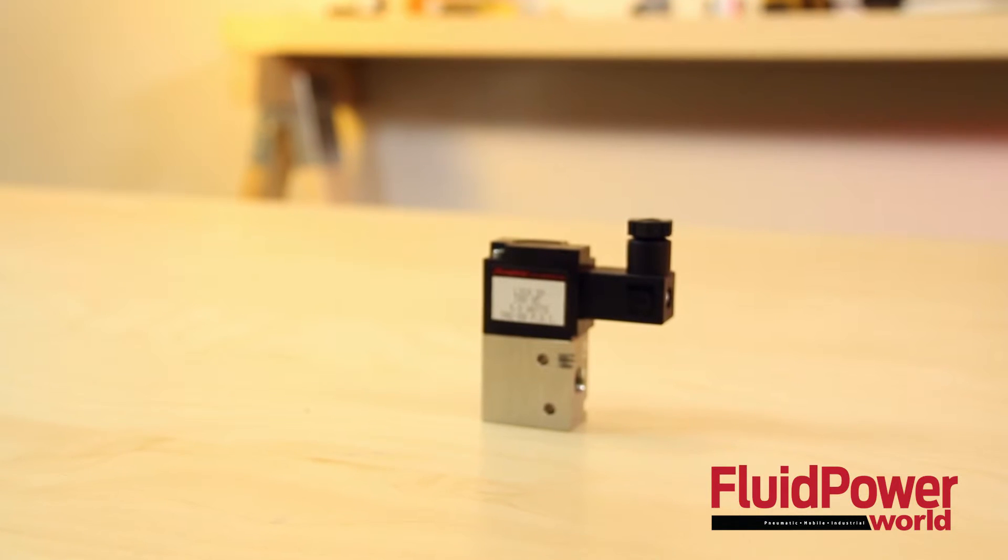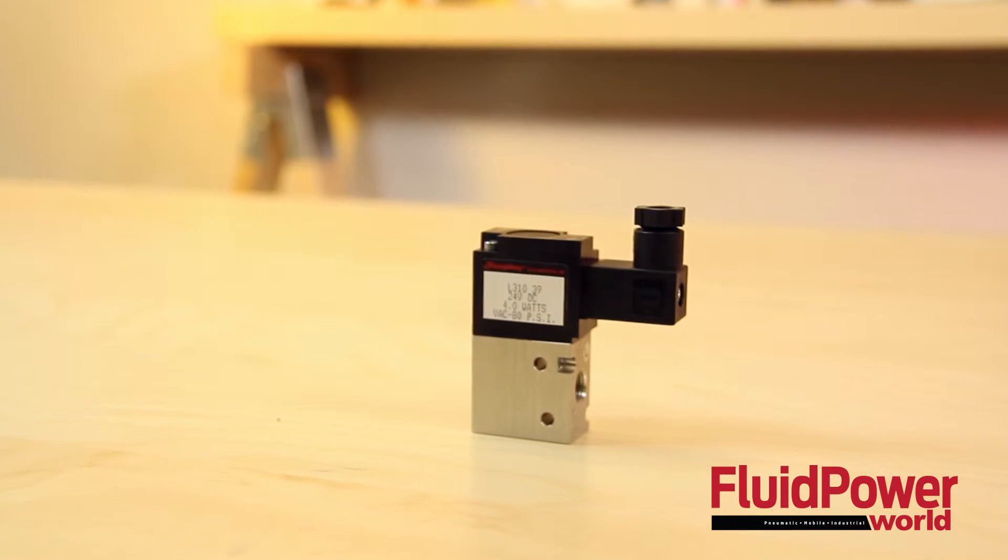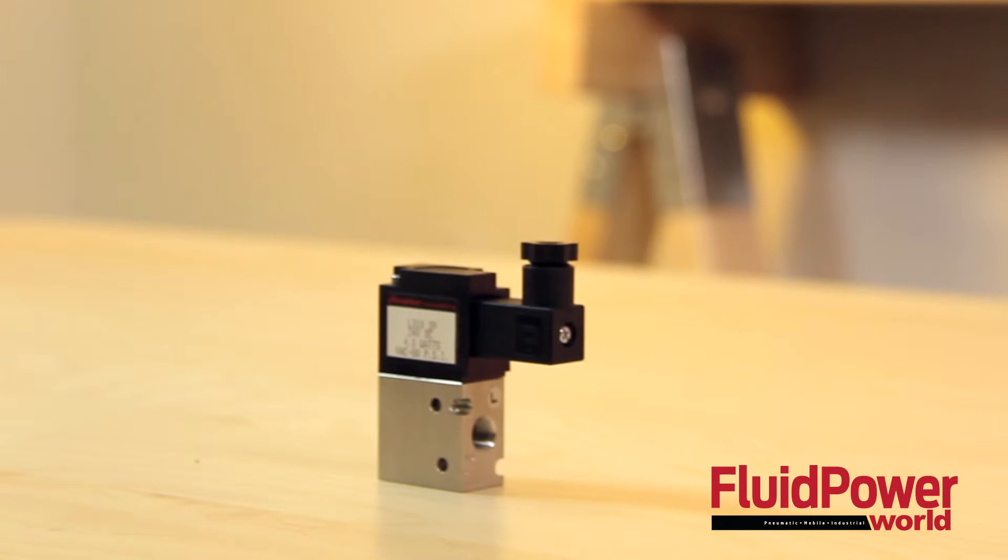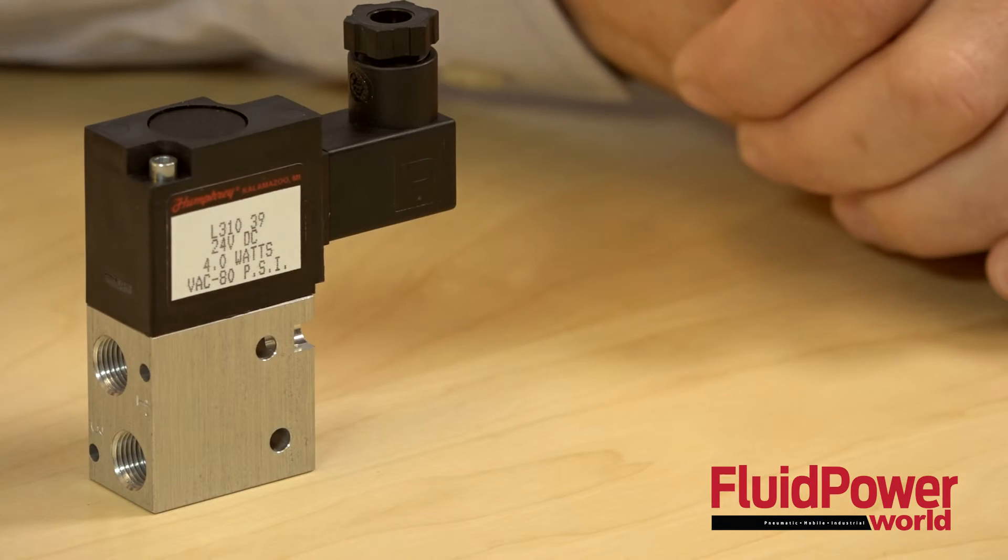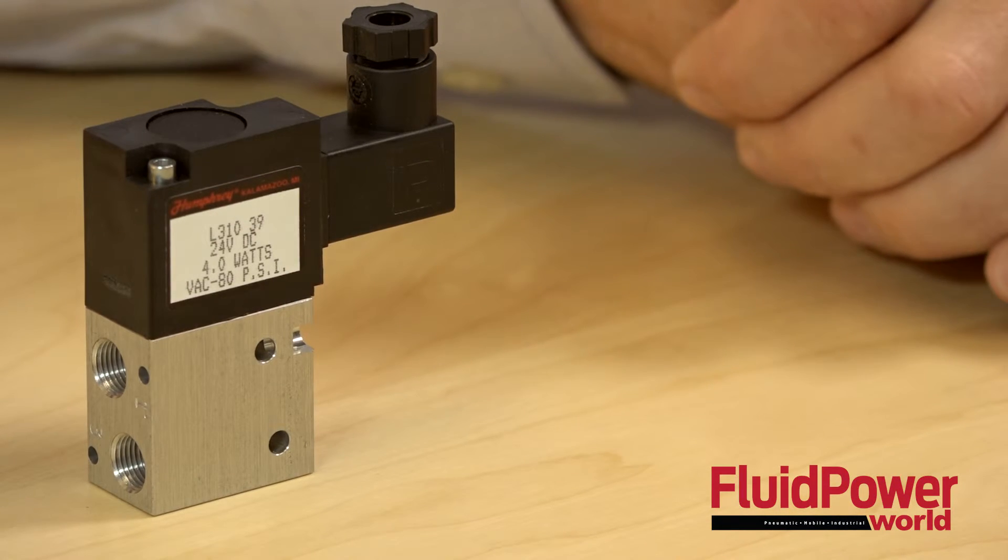The L310 is of a balanced construction and therefore it is suitable for vacuum or pressures up to 80 PSIG as normally closed or normally open functions. It can be used on the 410M manifold in conjunction with or without Humphrey's 310 and 410 series valves.